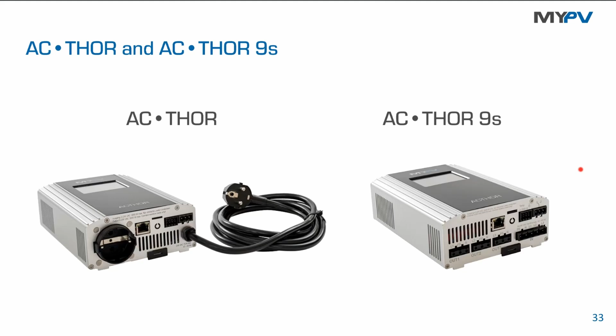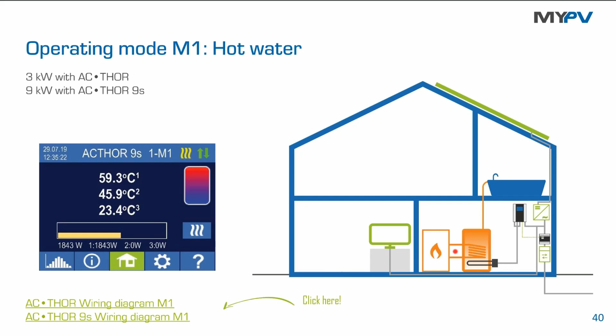The most important one is this mode 1. It's let's say for a 9 kilowatt immersion heater for the ACTHOR 9S, and this means in an installation like this, you can use most of the energy for your own. You can connect a 9 kilowatt heater or also a 6 kilowatt heater or a 4.5 kilowatt heater to the ACTHOR 9S, and it will detect the nominal power of this load automatically. And up to 9 kilowatts are possible. And when you assemble such a heater at the bottom of the tank, it means that you have the whole volume available for heating. This means high self-consumption ratio. The disadvantage on the other side is that it might take a long time to heat up the whole volume. Maybe you do not reach the target temperature during the evening.